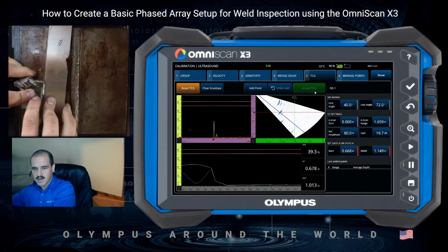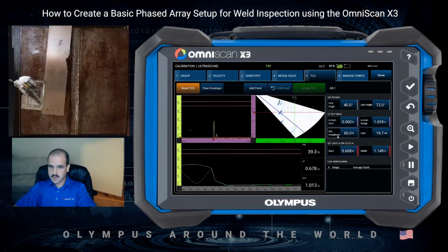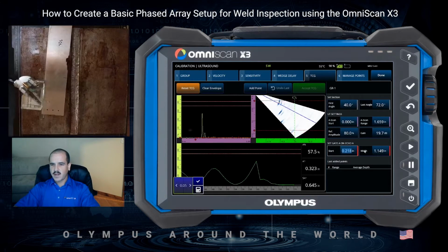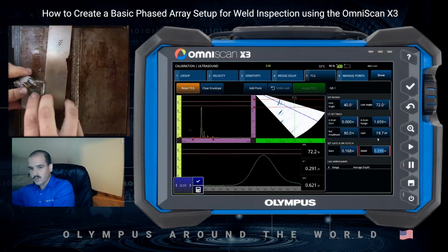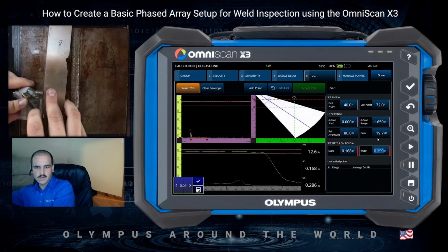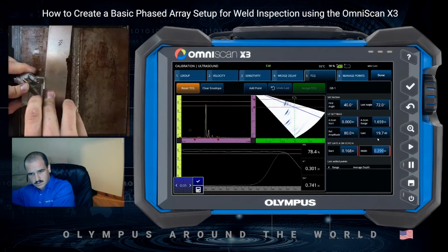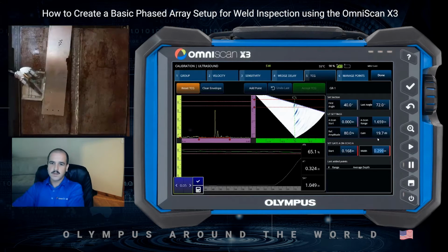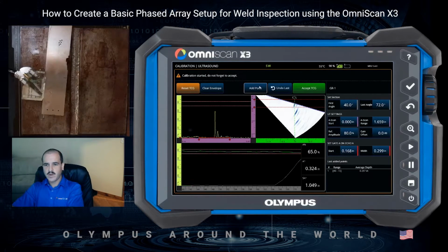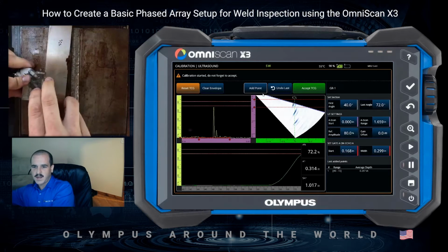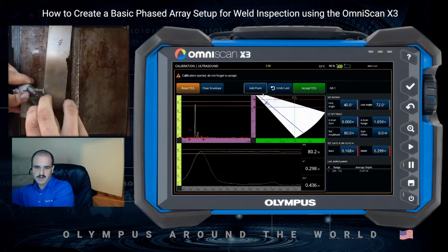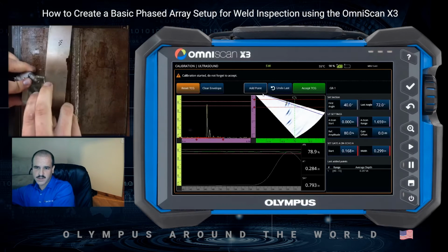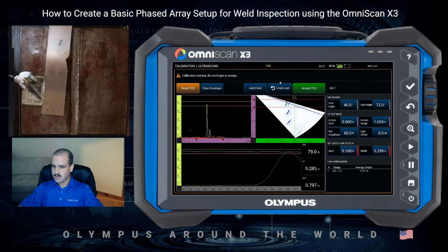So I'm just going to bump it back so I can get my holes on the screen, and I'll do the same as I did in the sensitivity calibration, where I set my gate A on my first point, do another raster across those holes. We're going to select add point. Once the point's added, we can just do a quick verification of that point, and now we're ready to move on to the next point. So there's no additional steps needed.